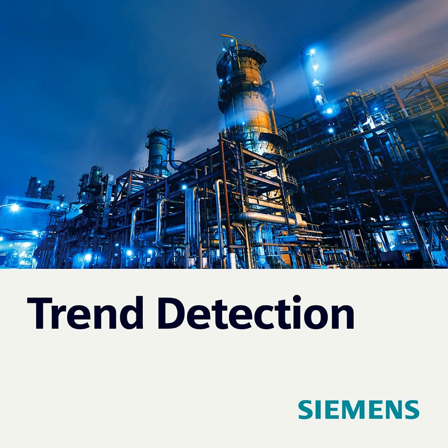We're trying to trend an asset or a machine that is doing the same thing over time, trying to compare apples to apples, if you will. So you're looking for repeatability. You're looking for operational conditions and characteristics from a machine that you can capture time and time again reliably. So that might be selecting a certain speed range from a machine that varies in operational speeds and identifying that as your test point and grabbing samples when the machine is in that condition.